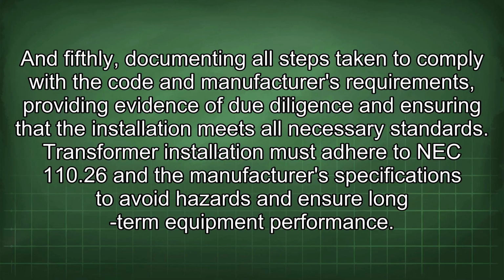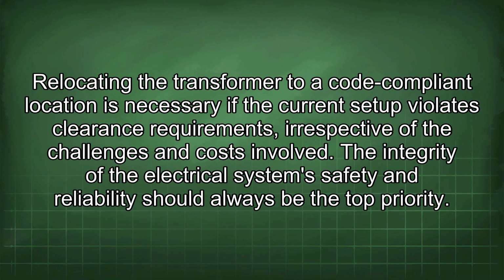Transformer installation must adhere to NEC 110.26 and the manufacturer's specifications to avoid hazards and ensure long-term equipment performance. Relocating the transformer to a code-compliant location is necessary if the current setup violates clearance requirements, irrespective of the challenges and costs involved. The integrity of the electrical system's safety and reliability should always be the top priority.